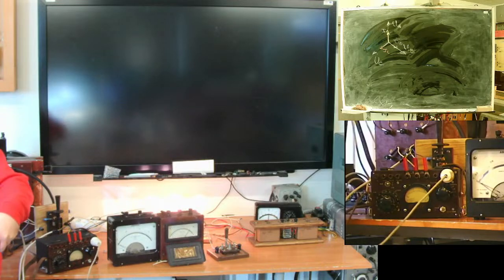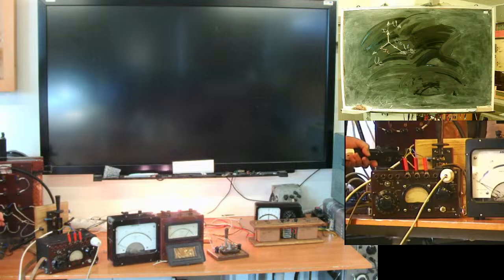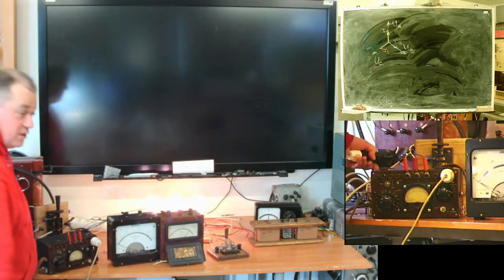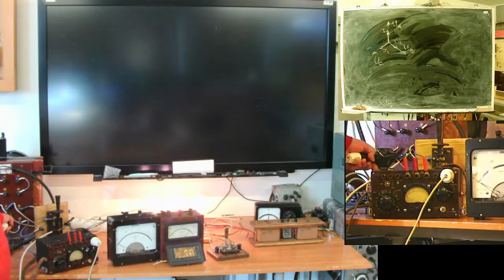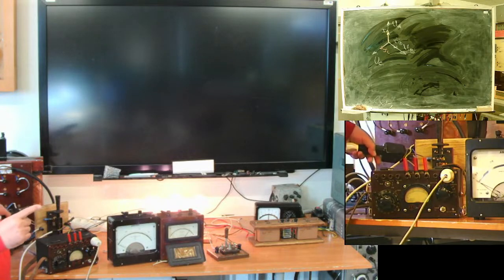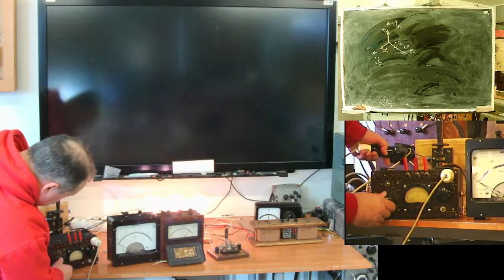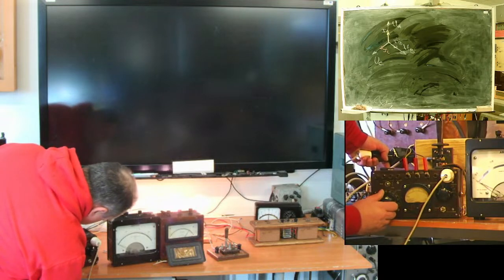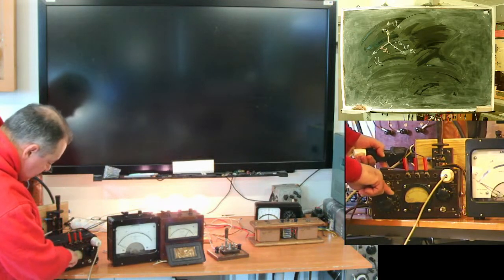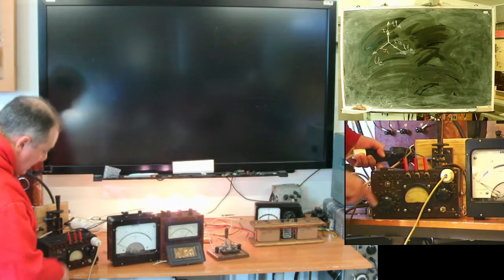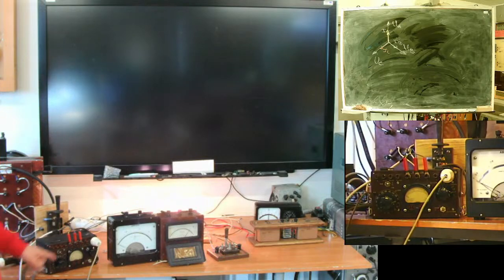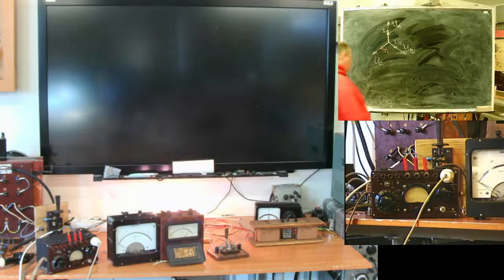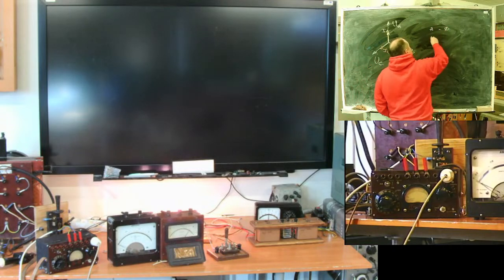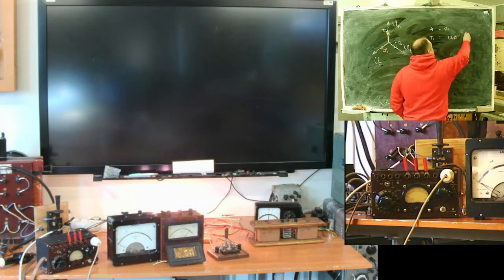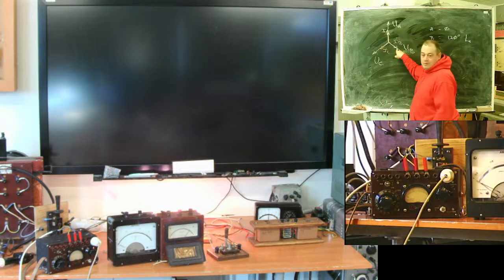It should inflow in the star, A phase inflows in. I have a 0 here. This means that the A phase current vector has the same angle as A phase voltage. Now let's see what with the phase B. 0 or not 0? Oh, now it's 0. And here is my reading: 120 and inductive, lagging. For phase B, for A, 0; B, 120, lagging.